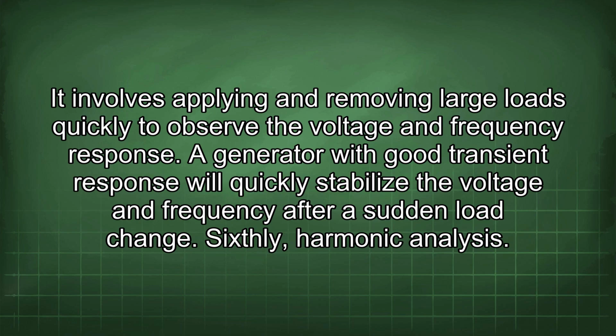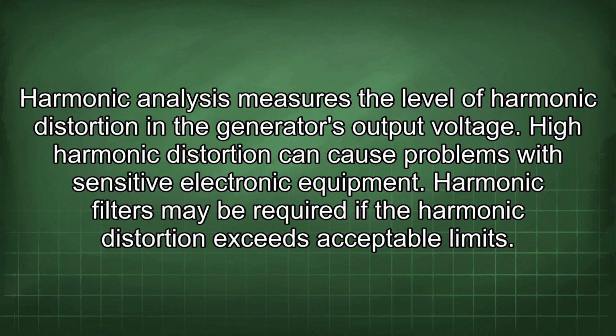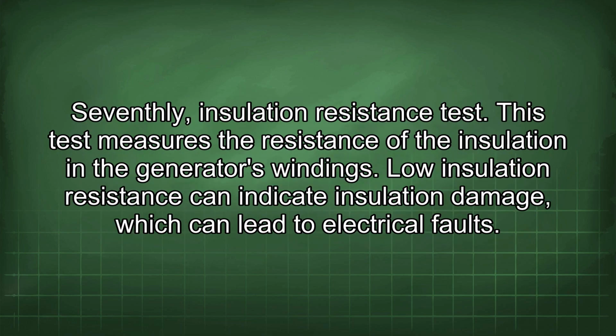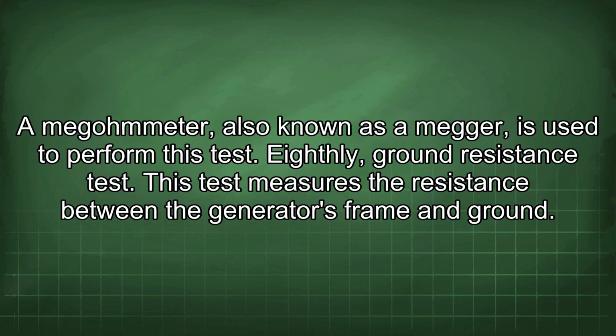Sixthly, harmonic analysis. Harmonic analysis measures the level of harmonic distortion in the generator's output voltage. High harmonic distortion can cause problems with sensitive electronic equipment. Harmonic filters may be required if the harmonic distortion exceeds acceptable limits. Seventhly, insulation resistance test. This test measures the resistance of the insulation in the generator's windings. Lower insulation resistance can indicate insulation damage, which can lead to electrical faults. A megohmmeter, also known as a megger, is used to perform this test.